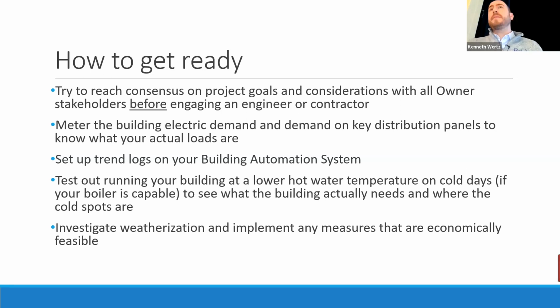And it depends, obviously. It depends how old the building is, whether it was air conditioned in the first place, but we're seeing with pretty consistent regularity that if, say, you have a 100,000 square foot building, it might have an 800 amp service. It's not unlikely you need to go up to 1200 or 1600 amps to support all this. So it could be 50% higher or double.